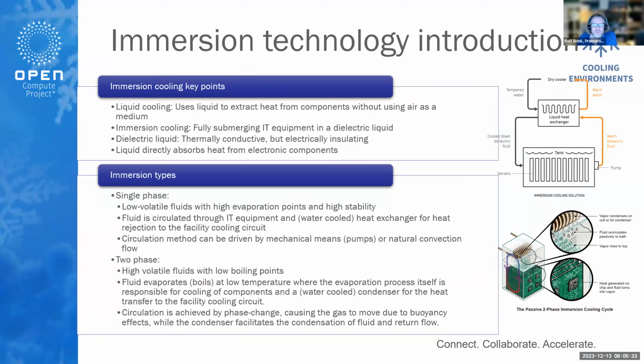I'm going to skim over this a little bit because I don't want to make this a very technical session, but if you're not familiar with immersion cooling, a couple of key points: we need to differentiate between generic liquid cooling, cold plate cooling, and indirect liquid cooling, like with door heat exchangers. Liquid cooling in general is just the practice of using a liquid to extract heat from components as opposed to air, whereas immersion cooling is looking at the full submersion of electronics within a dielectric fluid.